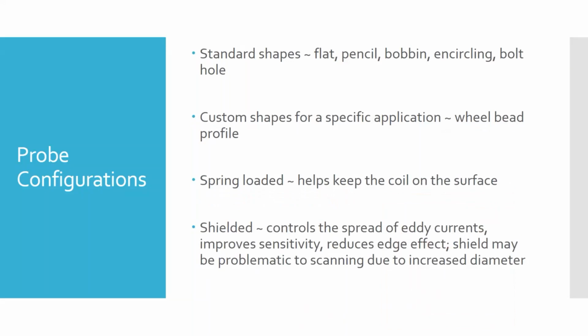So they'll have a shield that focuses or controls the spread of eddy currents so that they stay directly underneath the probe. And this avoids some of the effects of what's called edge effect, which is when you bring a probe near the edge of a piece of material, you'll start to pick up that change in material, right? You've got metal there, and then next to it is essentially air at the edge, and so it'll cause changes in induction as you do edge effect.